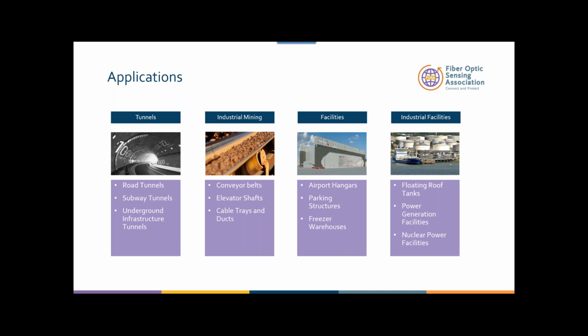And then we talk about industrial facilities. We have floating roof tanks and power generation facilities. In power generation facilities you have motors and different fans and equipment. The ability to run the fiber optic cable and literally change how the fire detection zone responds for each one of those areas is very important. We also have nuclear power facilities, where we use, let's say, hard rad, which is radiation-proof fiber, to detect different parameters within the system.